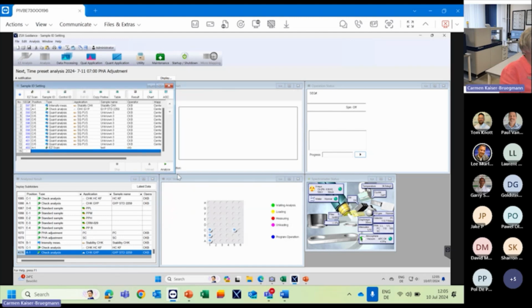So here we have a batch of samples, and you can see we have a mixture. We have check samples, and intensity measurements for a stability check. We also have some quantitative analysis and this semi-quantitative analysis. As we mentioned before, we have two loading systems. One is for pre-evacuation of vacuum, and the other is for measurement of the sample here. So, of course, if I now say analyze, I will show you the picking up of the sample.